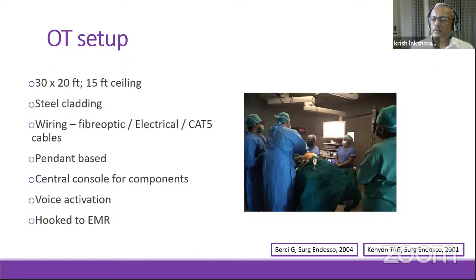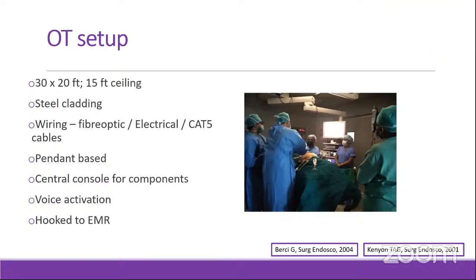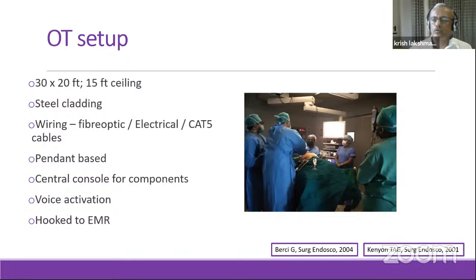The point is that in laparoscopy, you can be standing at the foot end of the table, or the head end, depending on the operation. You can be standing to the patient's right or left as a surgeon. So you need a minimum of two monitors, because if you're standing to the left of the patient, the monitor is in front of you, to the right of the patient. My assistant and the nurse are on that side, and they must also see what you're doing to help you properly, which means there must be a slave monitor behind the surgeon—a second monitor—so the assistant and nurse can see what's happening. So you need two monitors.